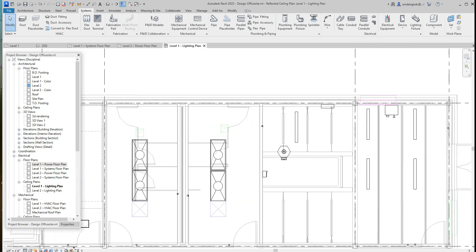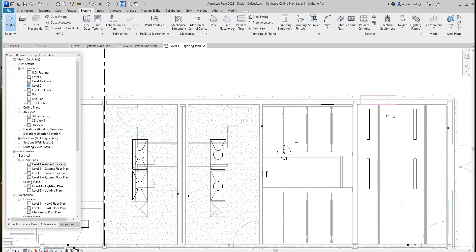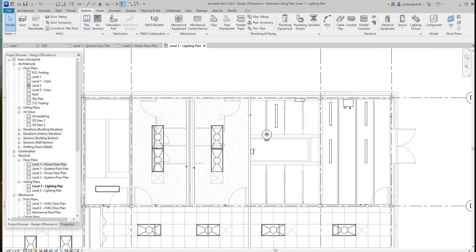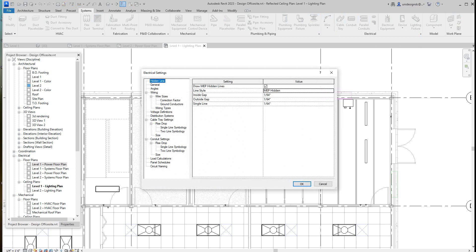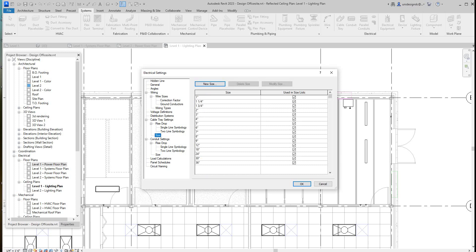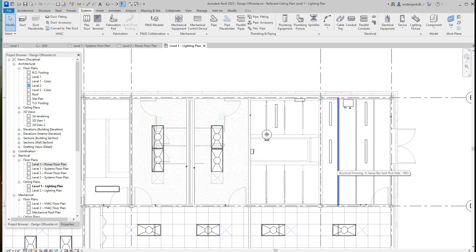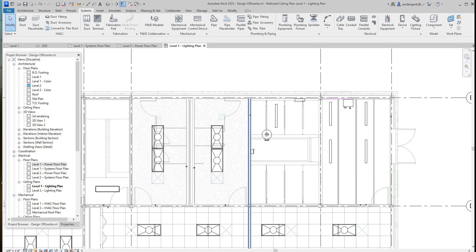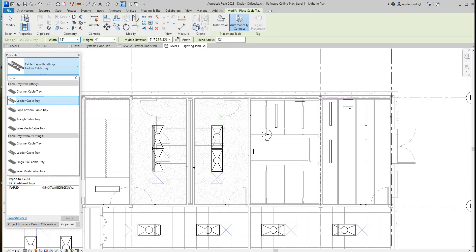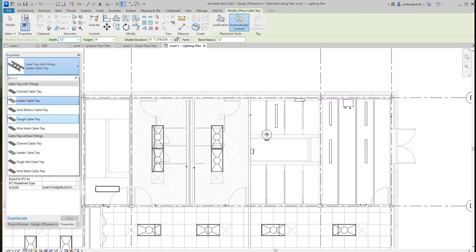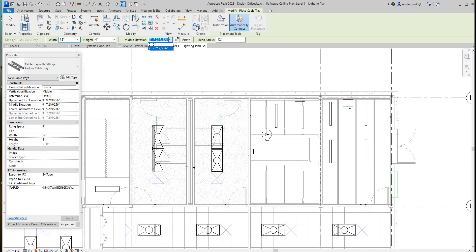So this is what I would do. First of all, I want to show you how this works. You want to be in the Systems tab, and in the Systems tab here you have cable tray. Then down here under electrical, you can select this and then here you have all your cable tray settings and sizes. So basically what I would do for this, this is probably your best view. I would go here and select cable tray. And then here, if I look at my properties, I've got a whole selection of different cable tray uses, but for us I'm going to go with ladder. And I'm going to set this at nine feet for right now.